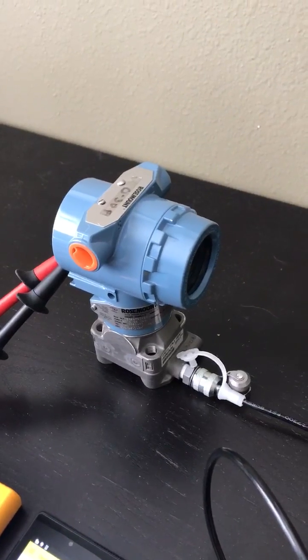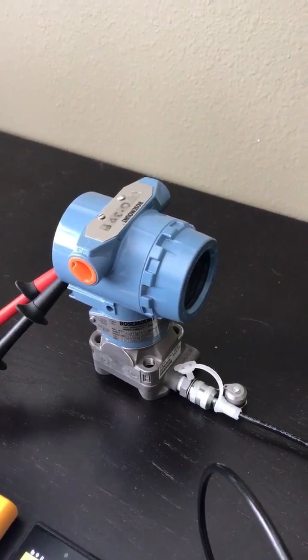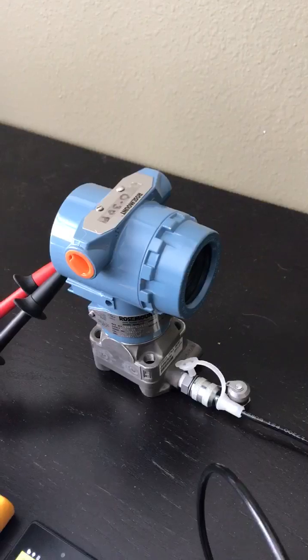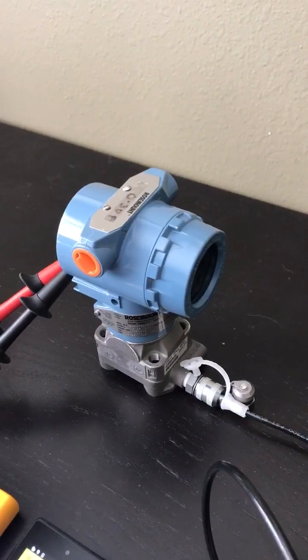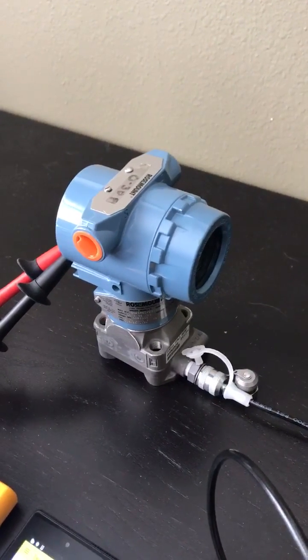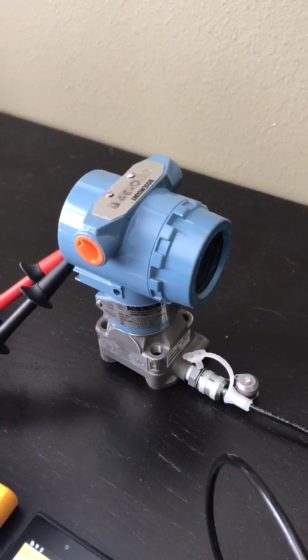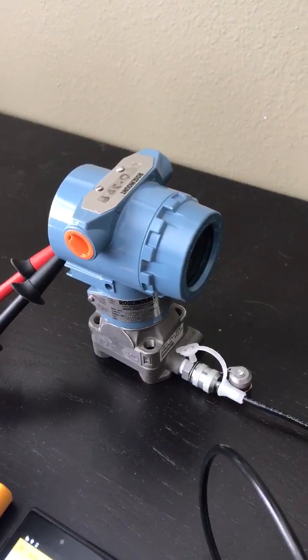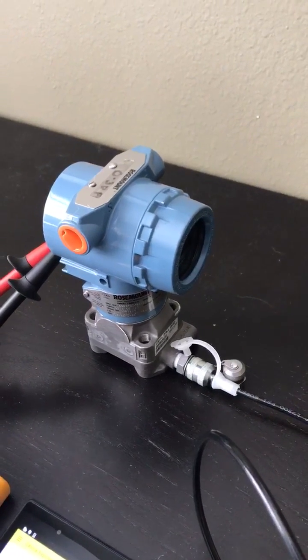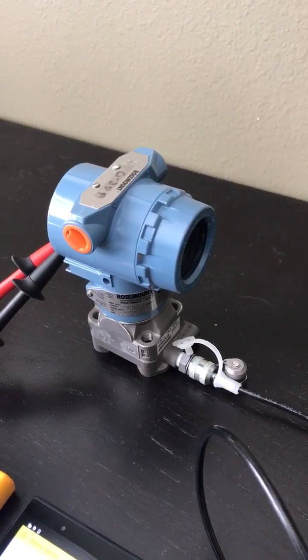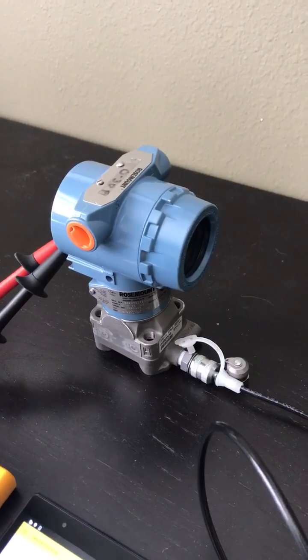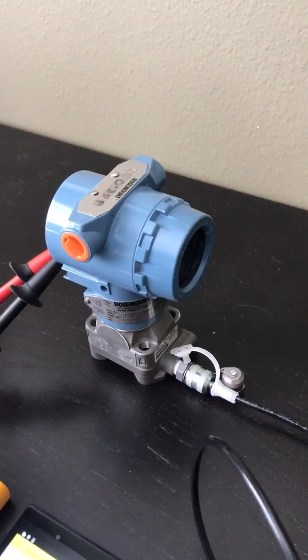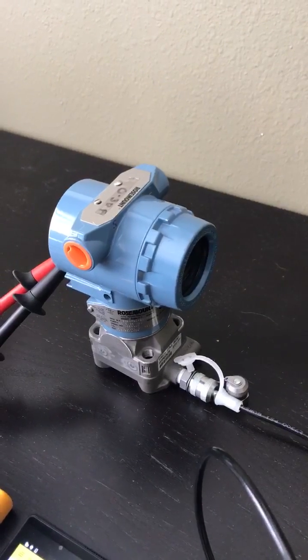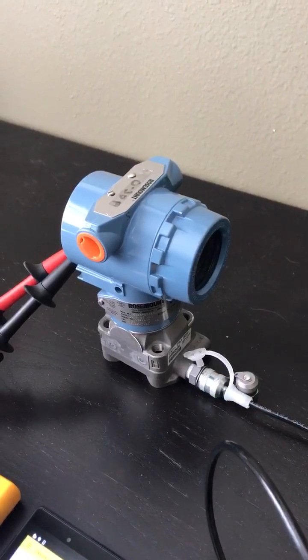Aaron from Fluke here. A very common pressure calibrator setup is often not a multifunction at all. It's three independent instruments that allow you to provide a source pressure or a known source to the transmitter, read the electrical output and possibly power the transmitter, and then, in the case of this smart transmitter, use a communicator to digitally adjust the transmitter.